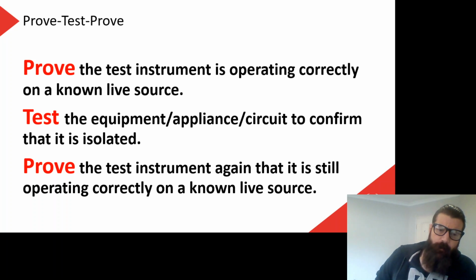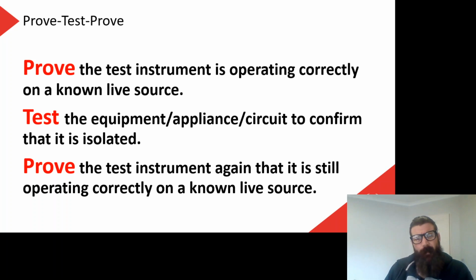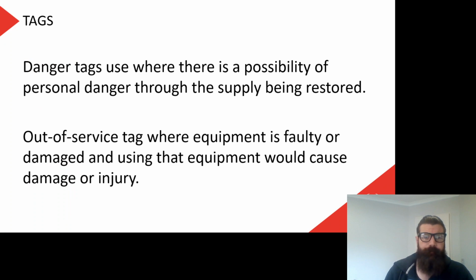As I said, this is generally when we're doing voltage. We're testing for voltage. We would look at doing the two prove, test, prove like that. But even that's the main one for safety. But if I'm testing for resistance or continuity, a good little prove, test, prove is I touch my meter leads together, and I should see a very, very low resistance, 0 ohms or pretty close to 0 ohms, just the resistance of the meter leads. And then I do my test, and then I touch them together again, and I know that meter is still working and testing resistance correctly.